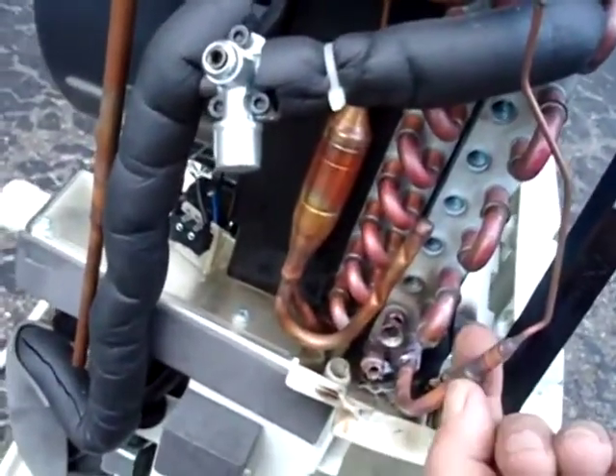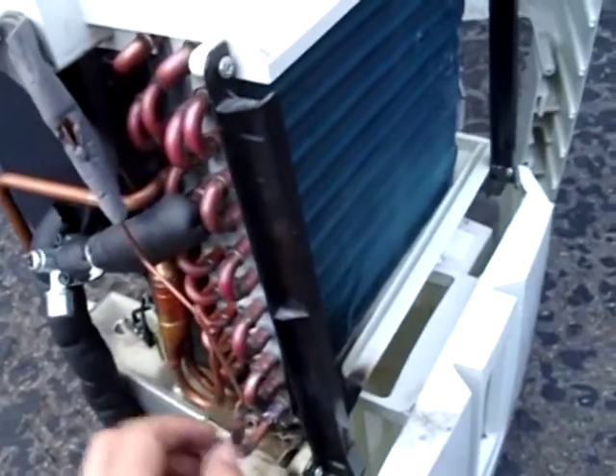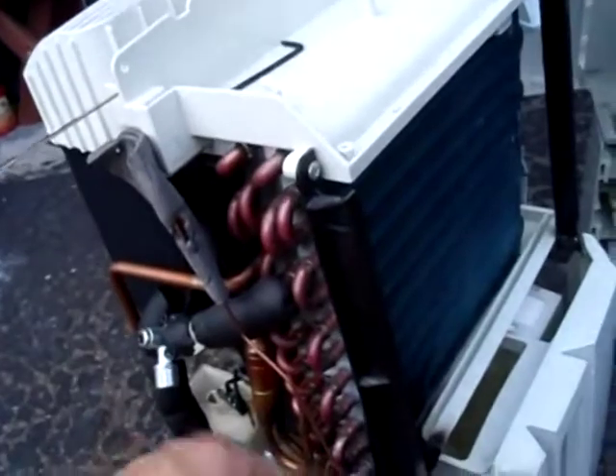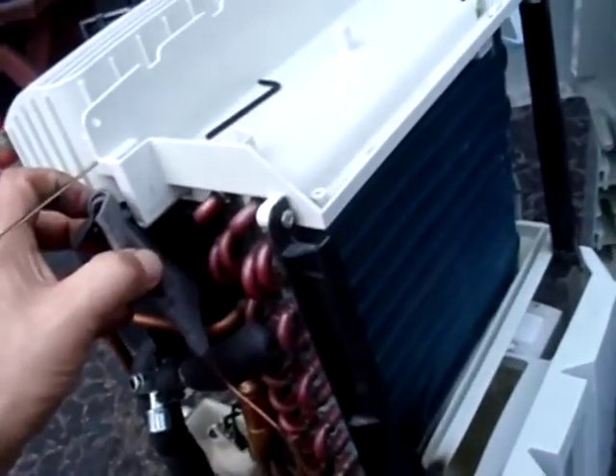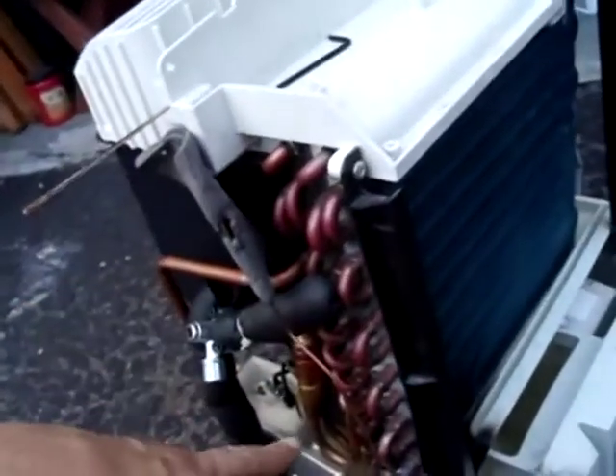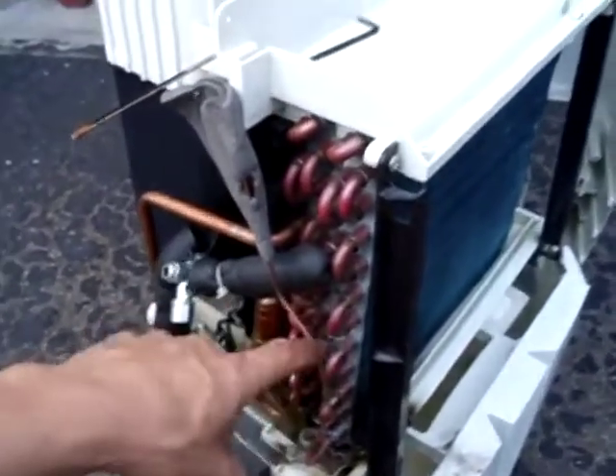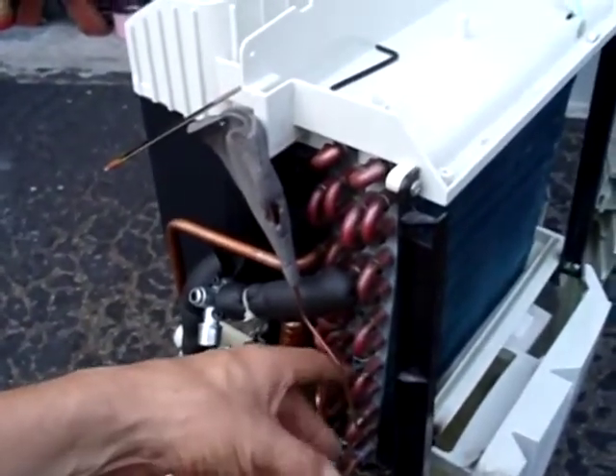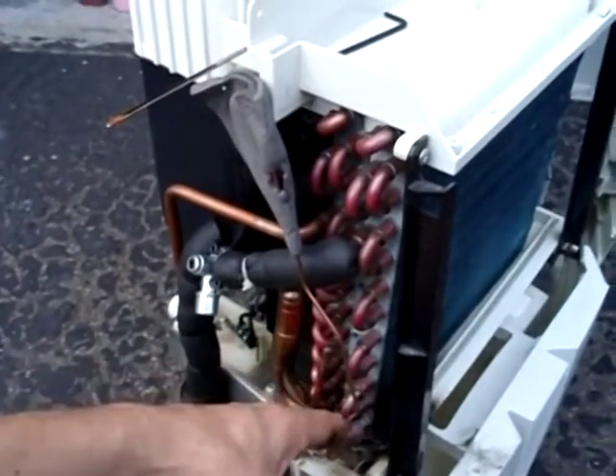This one came nice. With the oxyacetylene torch, you just have to put it there a little bit, and then it's hot enough, it sucks it in and melts it in. So then I put a little twist here. I'm pretty sure this is now outside the body, and this is in the wrong place. So I have problems, but I don't really care. It's probably going to the dump. So the next thing is, I've got to verify if it's sealing before I put in refrigerant.